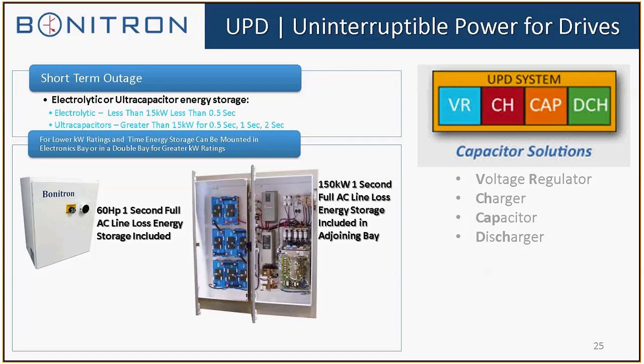One would hold the electronics, which actually includes all the modules except for the capacitors. It's going to include the discharger, charger, voltage regulator, booster, and the Ultracaps will go in the cabinet next to it. We can actually mount the energy storage cabinets on the back side, which is what we did for Samsung. So some of these things need to be worked out prior to quoting, and that would be one of them. How do they want to configure the cabinet system?